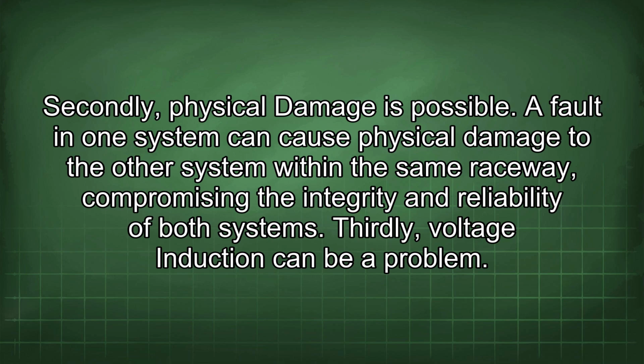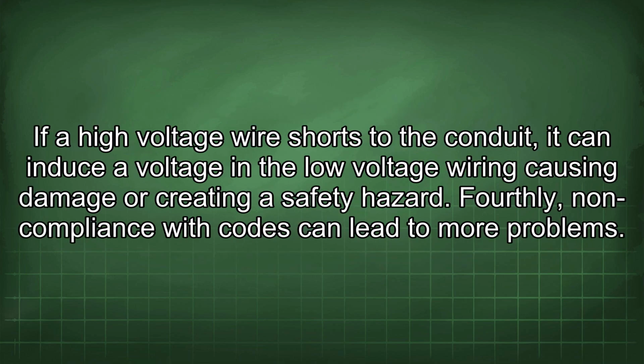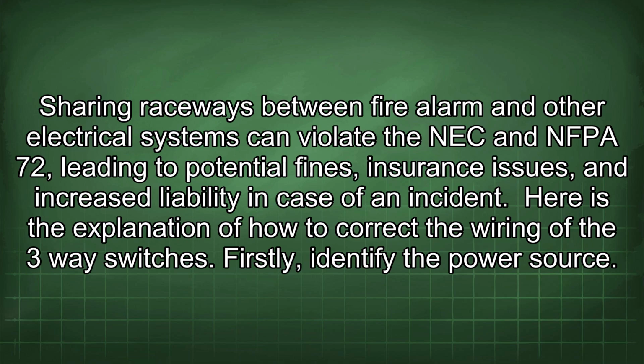Thirdly, voltage induction can be a problem. If a high-voltage wire shorts to the conduit, it can induce a voltage in the low-voltage wiring, causing damage or creating a safety hazard. Fourthly, non-compliance with codes can lead to more problems. Sharing raceways between fire alarm and other electrical systems can violate the NEC and NFPA 72, leading to potential fines, insurance issues, and increased liability in case of an incident.